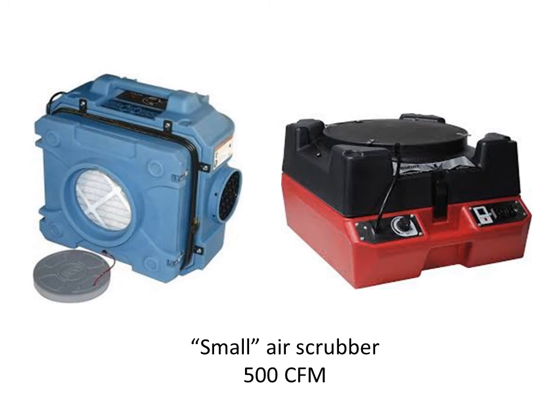Now on the flip side, which might make a big difference for negative air. So for your negative air, if you don't want to be blowing particles out of your containment through the HEPA filter, set it lower. Inside containment, whether you set it lower or higher probably makes no difference, because if you set it higher, it just simply means it has a lower efficiency, but air is circulating through it more often, so more particles are simply going to be caught because of the number of air changes.